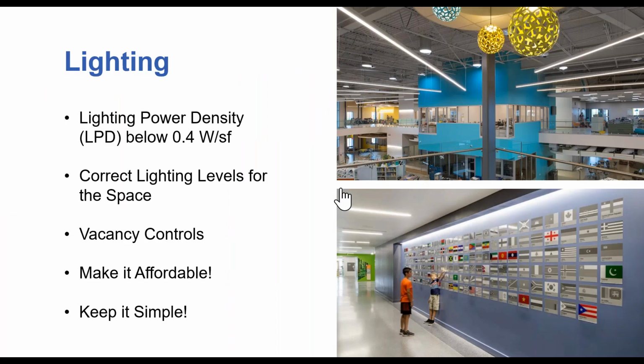Okay, lighting. I won't dwell on this for very long, but in general any zero energy school should be hitting less than 0.4 watts per square foot for lighting power density. We've got a couple of schools that have gone under 0.3 watts per square foot, but anything over that and you're really wasting energy. Beyond that, the only caution I'll give, from an affordability perspective, is: do not let the lighting salesman design the lights.